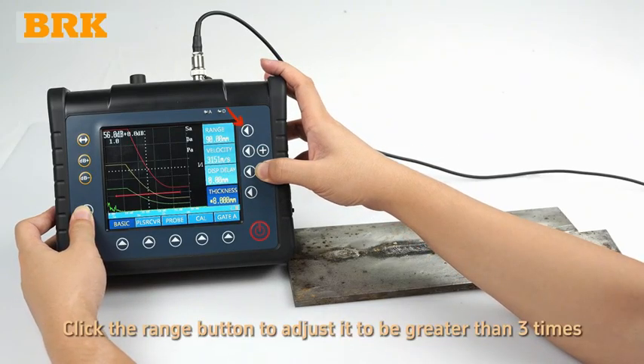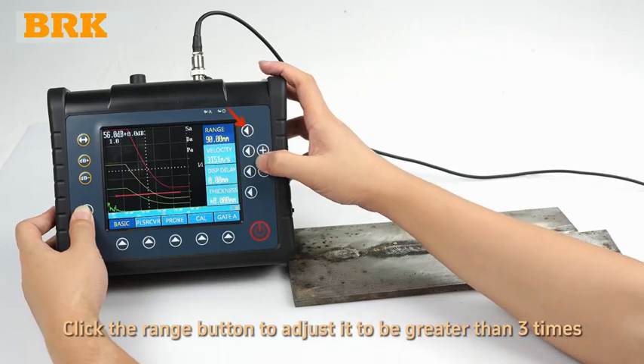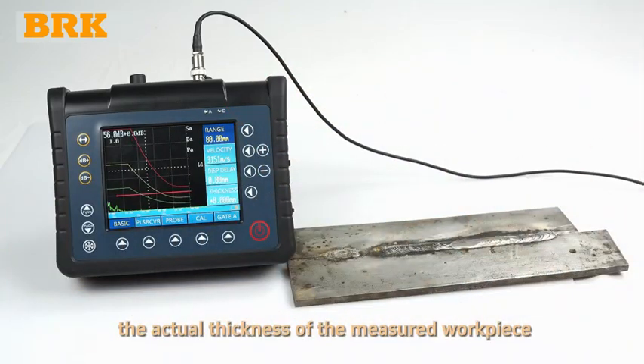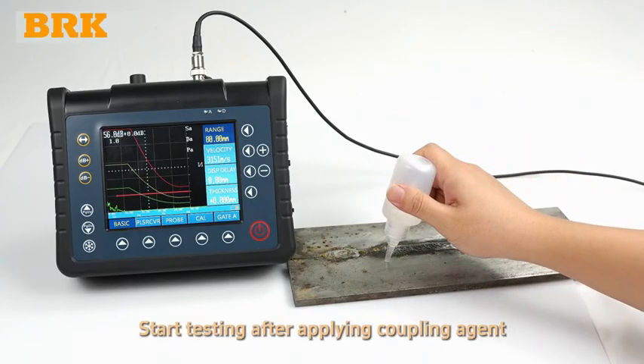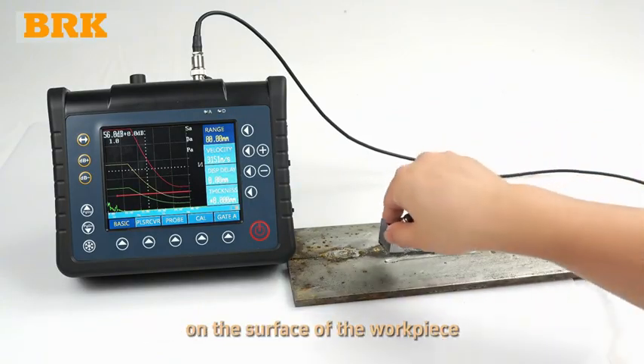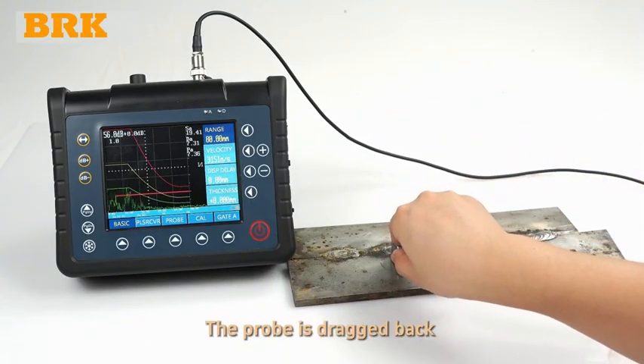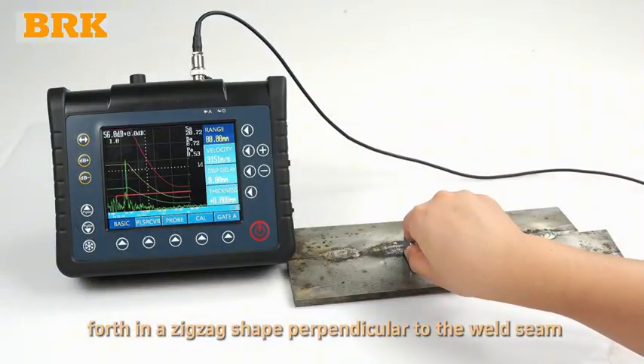Click the range button to adjust it to be greater than 3 times the actual thickness of the measured workpiece. Start testing after applying coupling agent on the surface of the workpiece. The probe is dragged back and forth in a zigzag shape perpendicular to the weld seam.